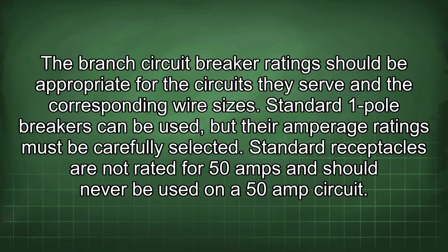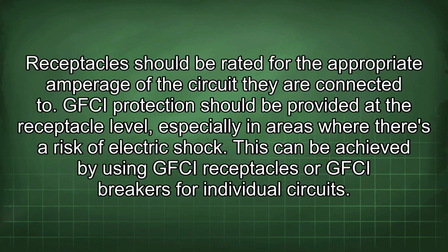Standard receptacles are not rated for 50 amps and should never be used on a 50 amp circuit. Receptacles should be rated for the appropriate amperage of the circuit they are connected to. GFCI protection should be provided at the receptacle level, especially in areas where there's a risk of electric shock. This can be achieved by using GFCI receptacles or GFCI breakers for individual circuits.